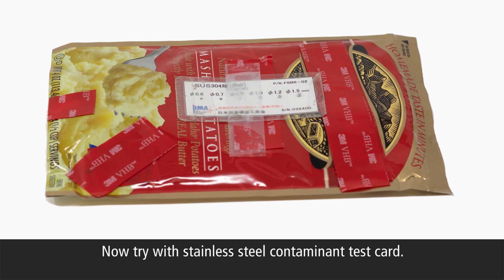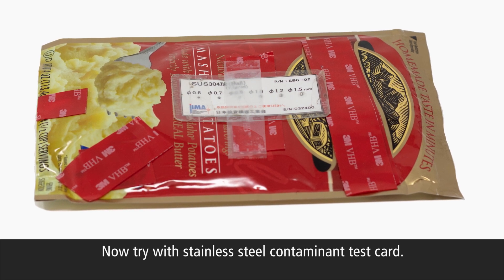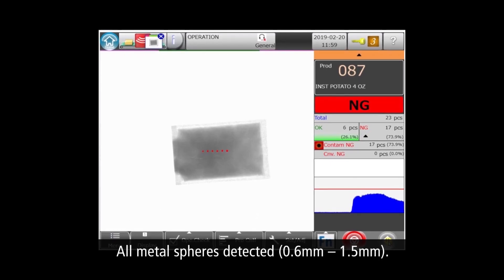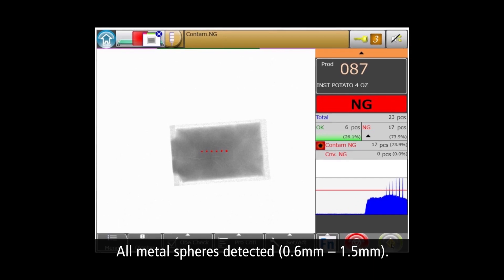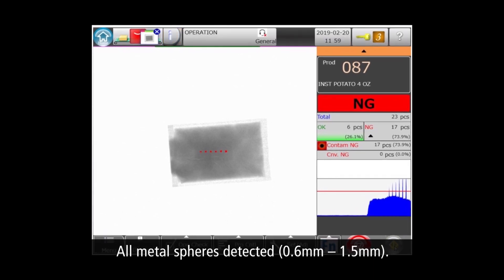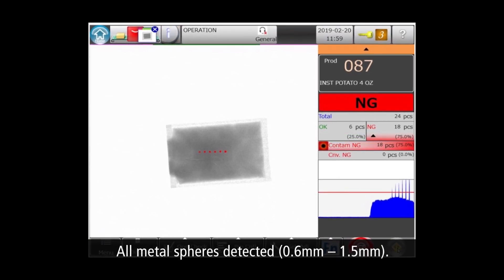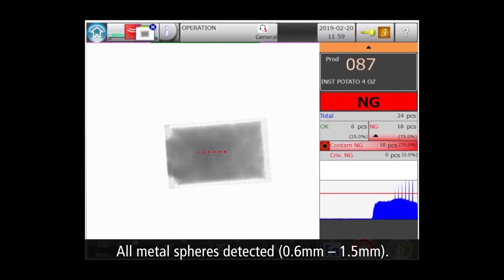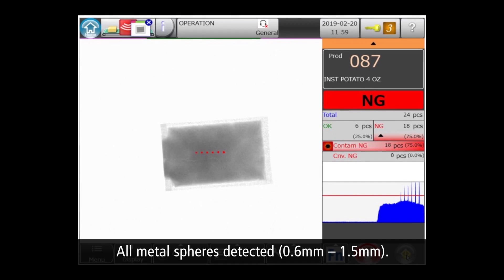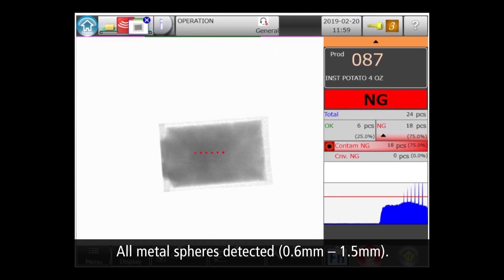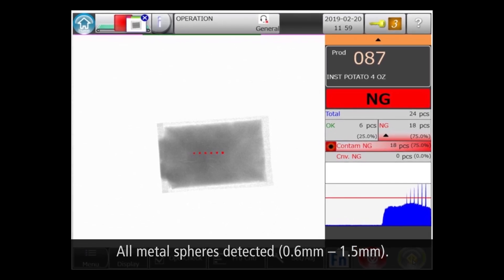The next step is to run a contaminant test. We attached the test card with certified stainless steel spheres to the product. And you can see by the red markers that the machine detected all six metal spheres ranging from 0.6 to 1.5 millimeters.